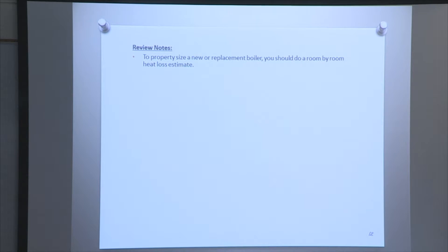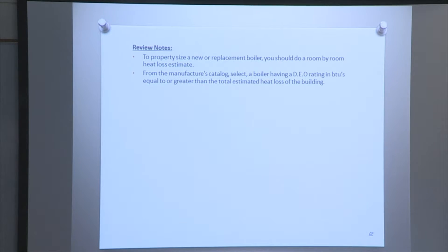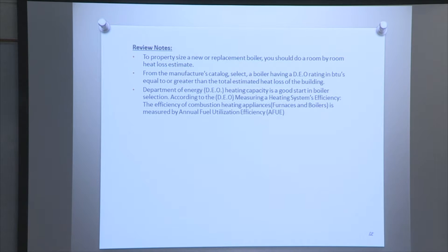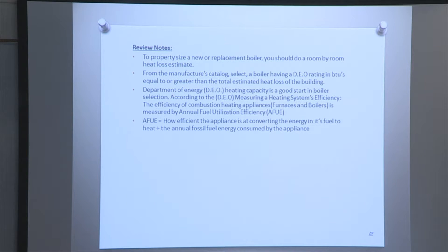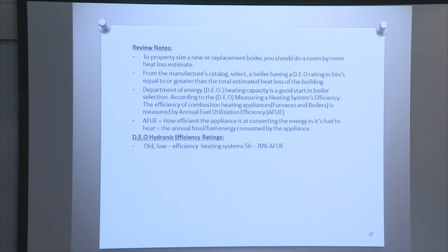Review notes: to properly size a new or replacement boiler, you should do a room-by-room heat loss estimate. From the manufacturer catalog, select a boiler having a DOE rating in BTUs equal to or greater than the total estimated heat loss of the building. Department of Energy heating capacity is a good starting point in boiler selection. According to the DOE, heating system efficiency — for furnaces, heating appliances, and boilers — is measured by the Annual Fuel Utilization Efficiency, AFUE. DOE hydronic efficiency ratings: low-efficient heating systems 56 to 70%, medium-efficient 80 to 83%, and high-efficient heating systems 90 to 98.5%.